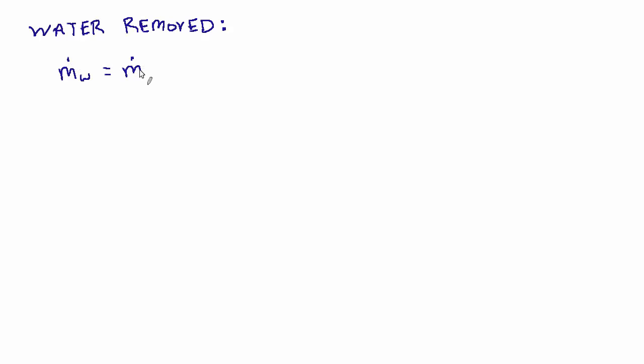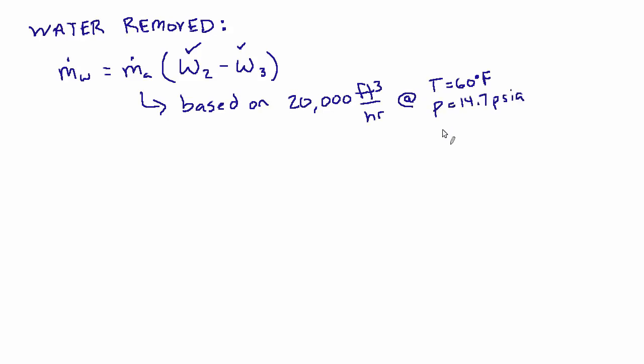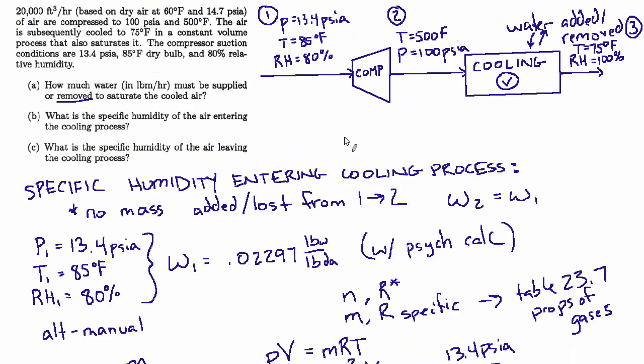It equals the mass flow rate of air times the difference in the humidity ratio, so humidity ratio at 2 minus humidity ratio at 3. And we know both of those values. But now the mass flow rate of air is actually a bit interesting. It says it has to be based on 20,000 cubic feet per hour at a temperature of 60 degrees Fahrenheit and a pressure of 14.7, and we also know that it's assumed to be dry air, so we can say a relative humidity of 0%.